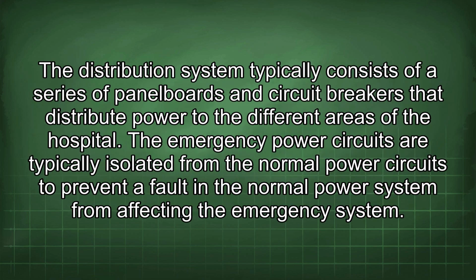The distribution system typically consists of a series of panel boards and circuit breakers that distribute power to the different areas of the hospital. The emergency power circuits are typically isolated from the normal power circuits to prevent a fault in the normal power system from affecting the emergency system.